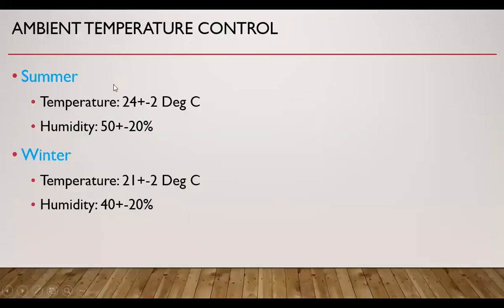Regarding ambient temperature control: the temperature of blood bank rooms should be 24 ±2°C in summer with a humidity of 50%, and in winter it should be 21 ±2°C with a humidity of 40%.